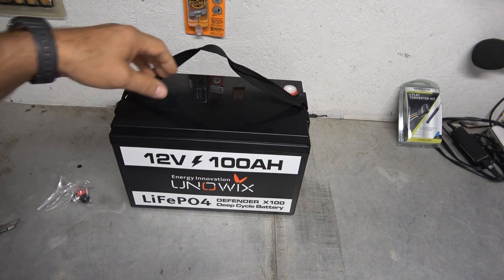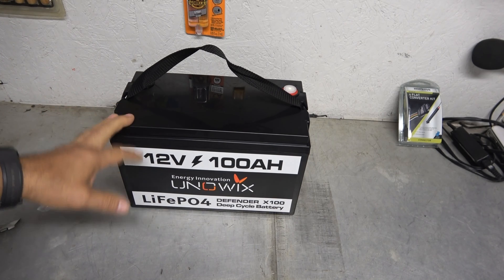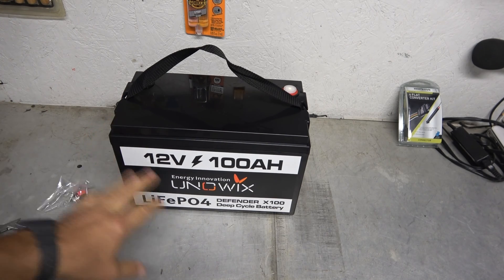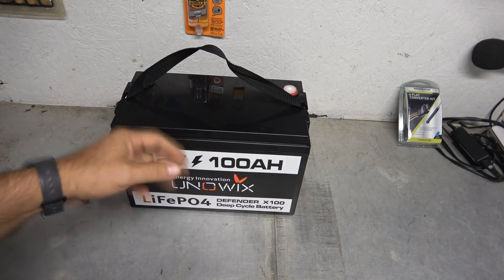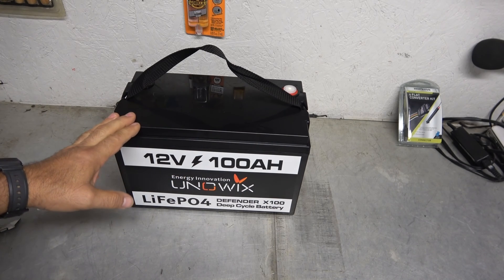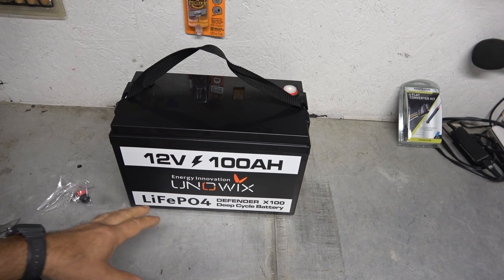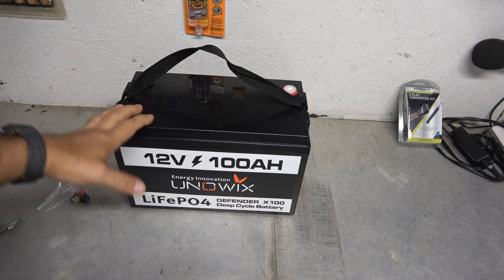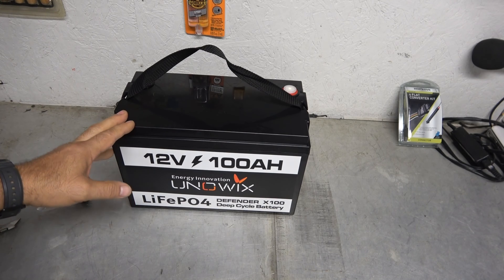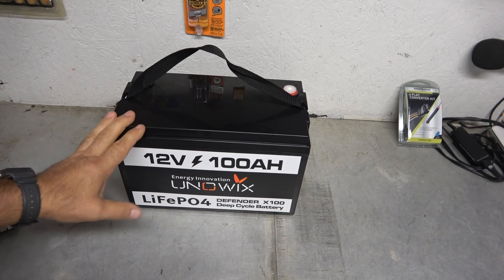12 volt, 100 amp-hour. If it's a deep cycle battery — conventional lead-acid or gel cell battery — you are only going to be able to use half of the rated amp-hour, and that's max. If you go beyond the half, you are going to start damaging the battery. On a lithium-ion battery, that is not the case. You can discharge this thing down almost to zero, and in some cases it's okay to go all the way to zero. So 100 amp-hours means 100 amp-hours.